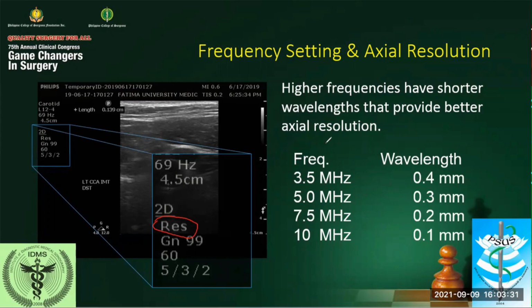It is dependent on the design of the machine. If the machine is using a multiple frequency transducer with a very wide range of frequencies, then the range for resolution, penetration, or general frequencies will be different. So in this case, you'll have to consult the user manual. But most machines would use numbers, so it's easier to see which frequency the machine is set to.